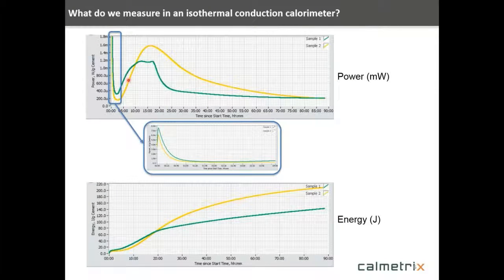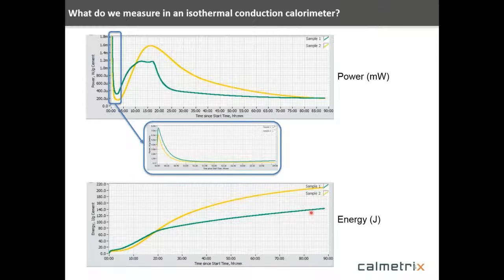The isothermal devices produce quantitative data — absolute power. If you integrate the power curve over time, you get energy. So another type of curve we look at is the continuous energy curve, plotting energy in joules per gram as a function of time. These are gradually increasing curves showing how much heat has been evolved from the sample over time. We use both sets of data in typical calorimeter applications.